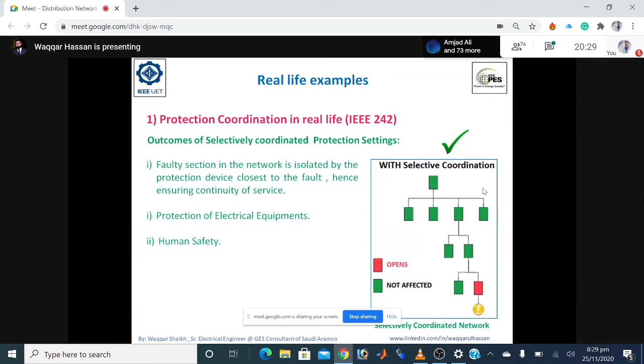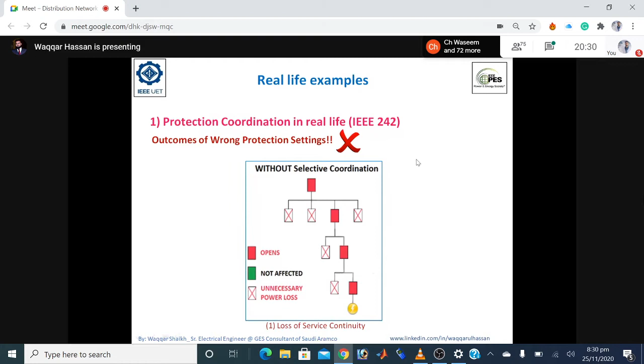If we are not doing the protection settings properly, it will firstly result in the loss of service continuity, right? You can see here, if the fault is propagating throughout the network, it will trip all the protection devices coming in series. And as a result, your production will be lost. Your factory will be blackout. Okay, so you don't want this scenario if you are the owner of a factory or a working professional. This is the minimum type of loss which can occur, because the other 2 losses are of higher nature, which I'm going to show in the next 2 slides. So this is one of the loss outcomes of wrong protection settings, that is loss of service continuity.